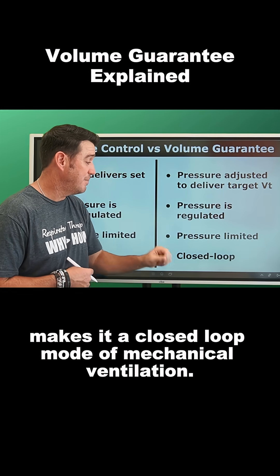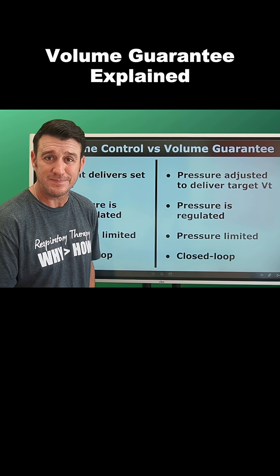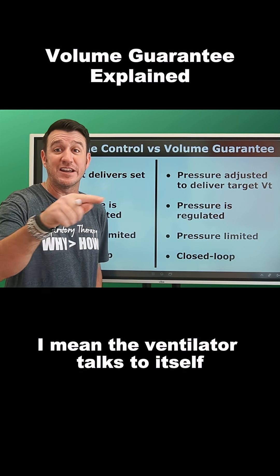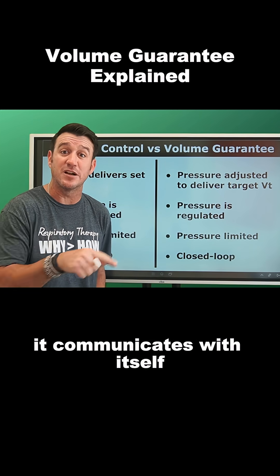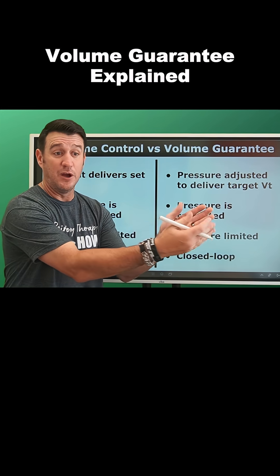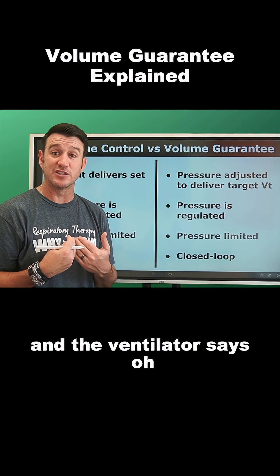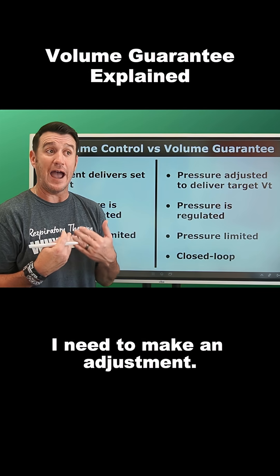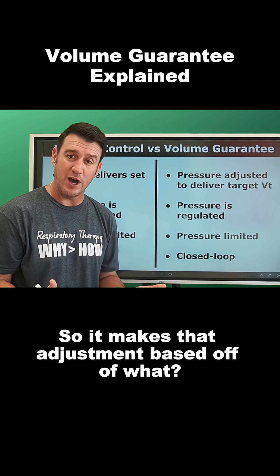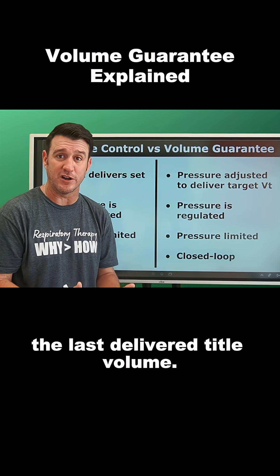That also makes it a closed loop mode of mechanical ventilation. When I say closed loop, I mean the ventilator talks to itself — it communicates with itself. It delivers a breath, feedback comes back from what happened with that breath, and the ventilator says, oh, I need to make an adjustment. So it makes that adjustment based off of what? Based off of the last delivered tidal volume.